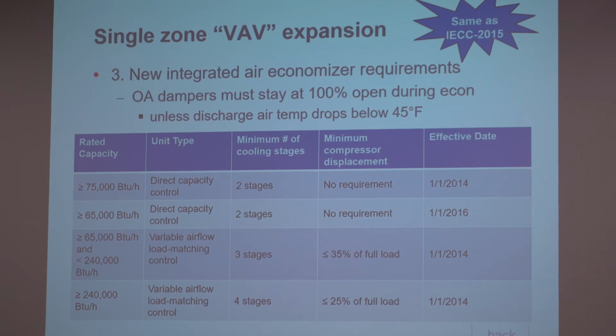This doesn't say that you have to cool to a specific dew point leaving your unit. It just talks about how small the compressors need to be, or how many of them there need to be, how many stages. But say your outside air damper must stay open. Oh, okay, so that's an economizer requirement. So, yeah, we're going to talk about that. If I need to maintain space humidity, yep, 55 saturated. You're right. I need to fit in an exception. So that's an exception for the economizer, but it's not an exception for this requirement.